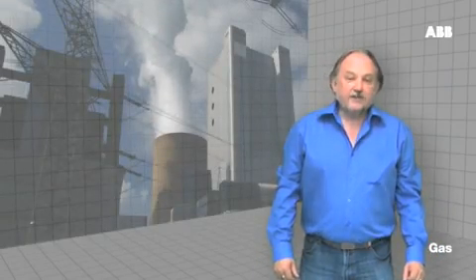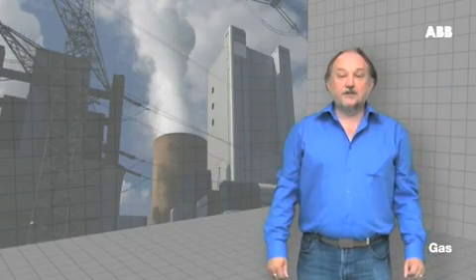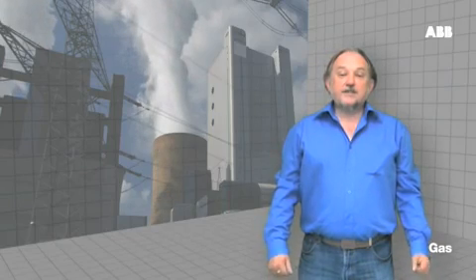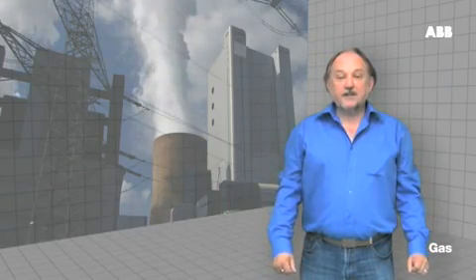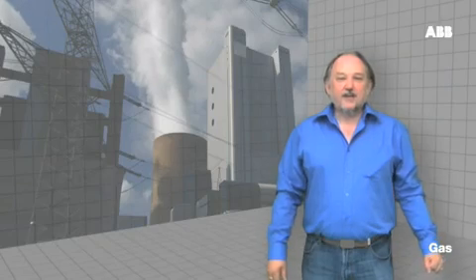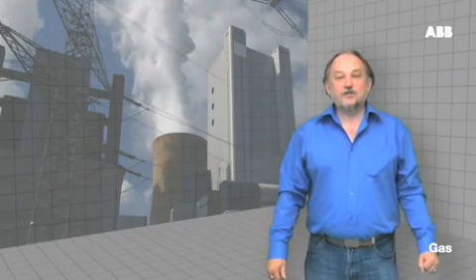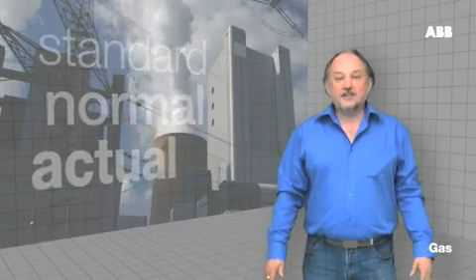In some areas of application and with some older equipment, standardised cubic feet are used, or SCF. These are expressed as if the gas is measured in cubic feet at 60 degrees Fahrenheit and one atmosphere. It is critical when making or comparing volumetric gas flow measurements to establish whether you are talking about actual, normal or standard units.